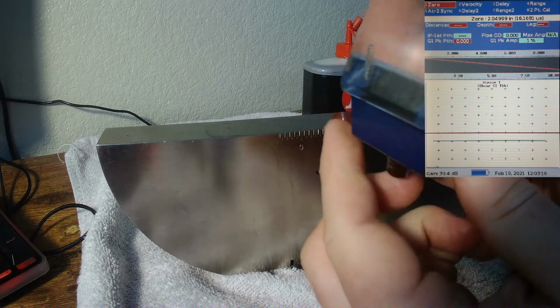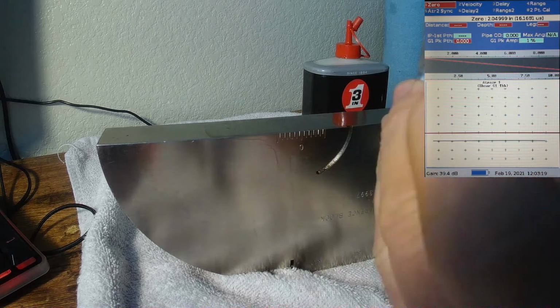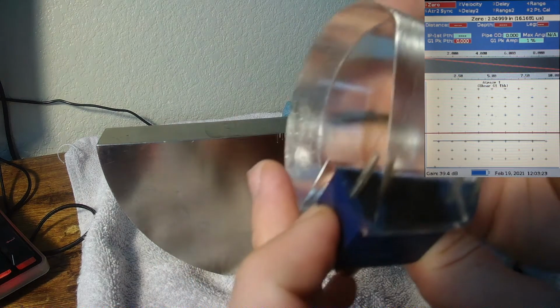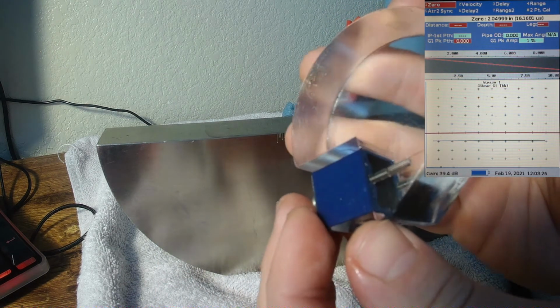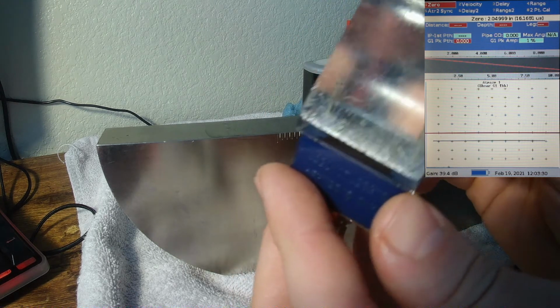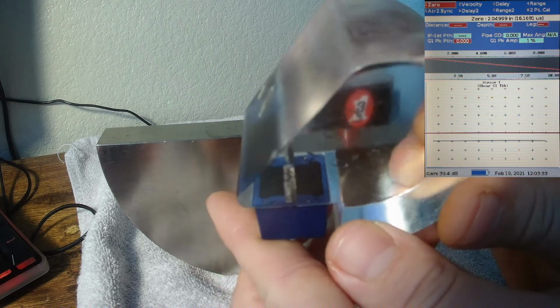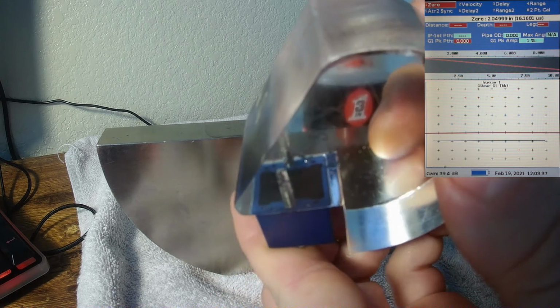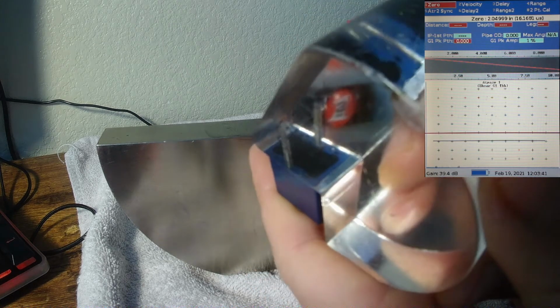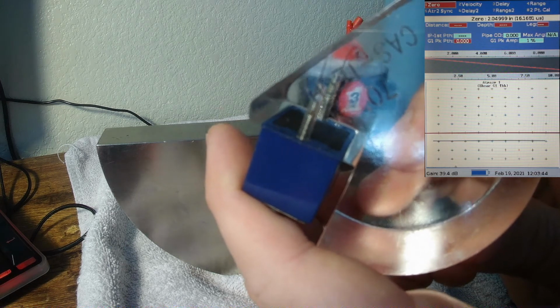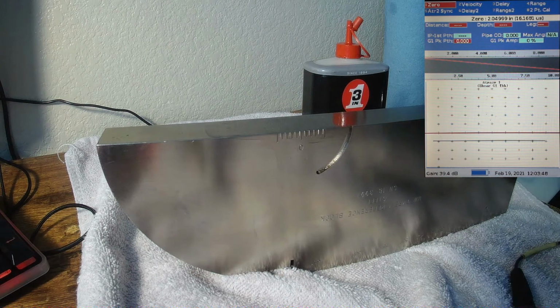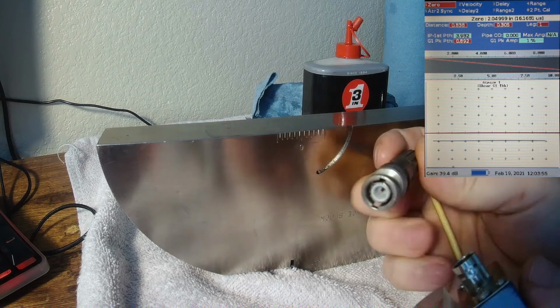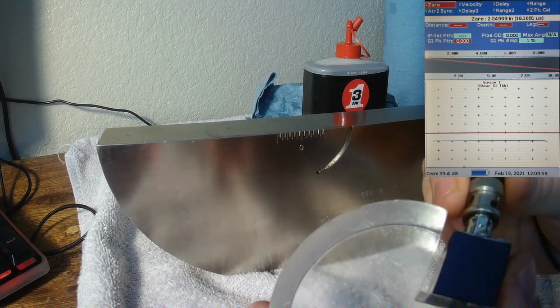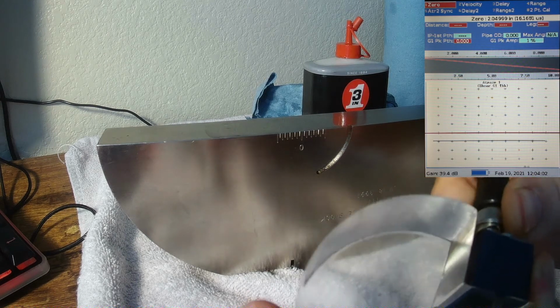All right, so let's look and make sure we have enough contact. Now, transducers like this style, they have some air holes next to the screws where you might see some bubbles, and that's fine. That's out of the actual transducer area, like that one up there. But looking around at the actual transducer contact area, it's looking nice. So now, clean it up a little bit more. Now we can hook up our BNC cable. Lock it in place.